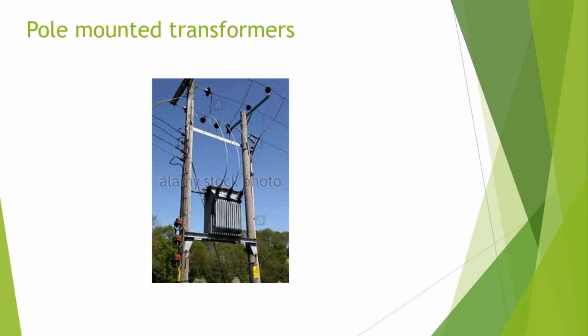Larger transformers are usually installed between 2 poles with a crossarm bracer between them. This type of pole arrangement is known as an H-pole and can also be found supporting 11 kV heavy construction lines and 33 kV lines. The transformer would be mounted below the overhead line conductors and would be connected using jumpers.